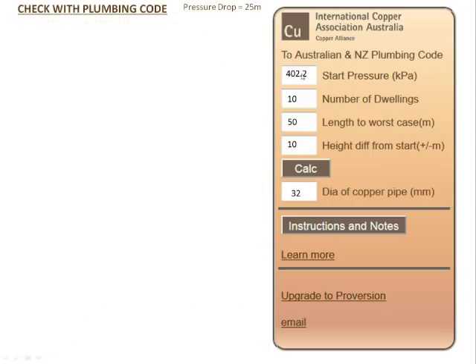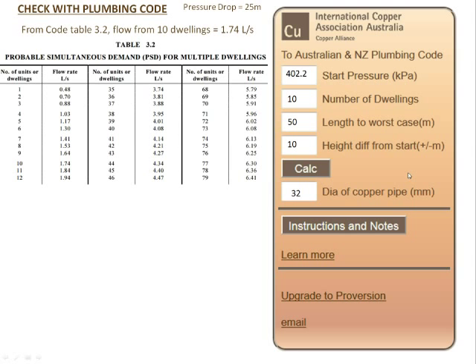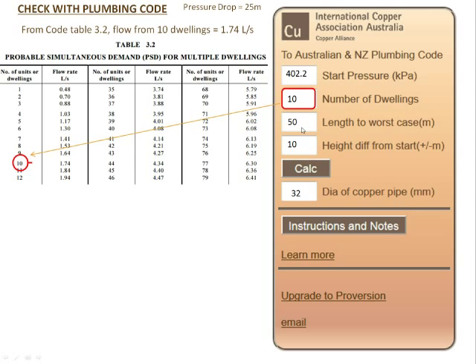Armed with this information — a pressure drop of 25 meters — we move into the code. From Table 3.2 in the code, for 10 dwellings, we get a flow rate of 1.74 liters per second.